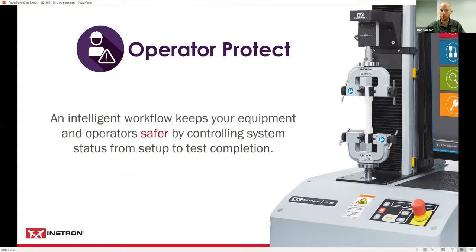So Operator Protect, our first feature, is really the new underlying system architecture, which helps mitigate the risk that the equipment poses itself. On our systems, operators are most exposed to these risks when they're setting up for their tests. The most common incidences on these machines typically fall into two categories. One is pneumatic grip pinches, and the other is unexpected movement during a jog or return action. By limiting the capability of the system when they're in this state, you can help keep your operators and your equipment much safer.